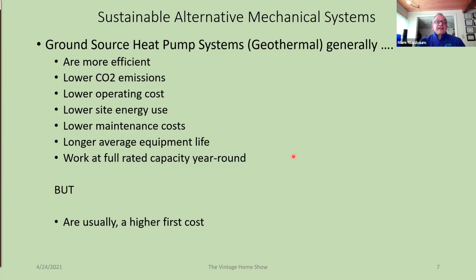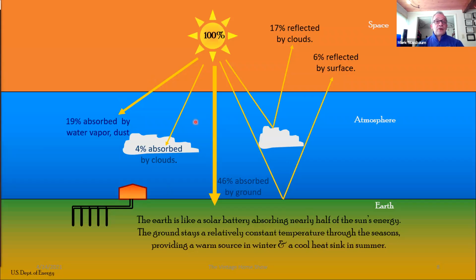As the temperature changes, and this is true of all heat pumps, as it gets colder, you have reduced capacity. But because we can design our well field, we can actually control how low that temperature goes, and so we can get full capacity year round. The caveat here is it's going to be significantly more expensive to install, because you've got to install the loop field.